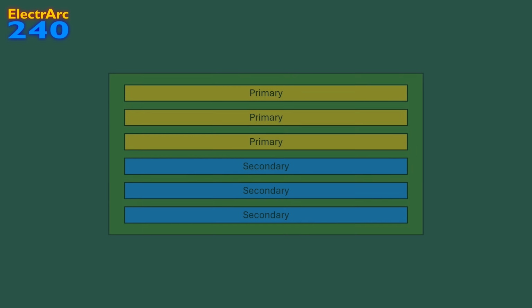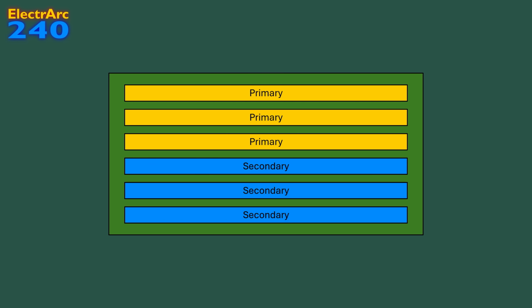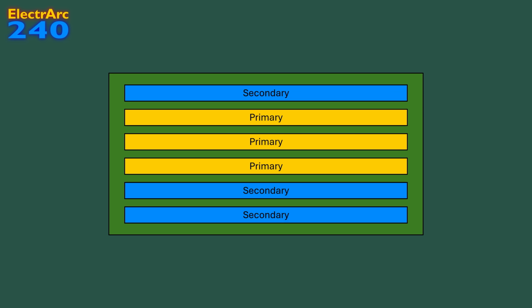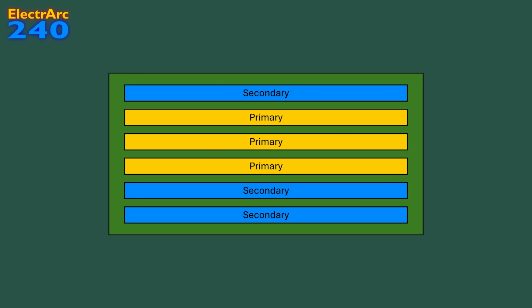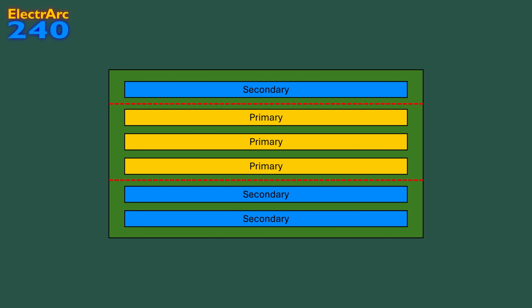A second thing that control of the windings' positions allows us to do more easily is interleaving. Instead of having all our primary windings and then all of our secondary windings, we mix things up a bit. This can range from a simple primary sandwich all the way up to a full-on zebra. Typically people stay closer to the sandwich style, because every time primary is next to secondary, we need some isolation, which takes up precious space.